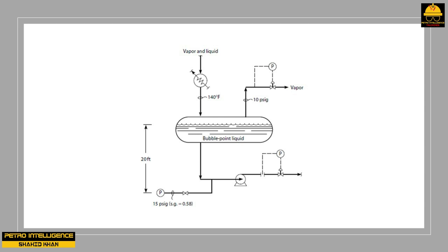As the flow control valve on the discharge of the pump is opened, the velocity of liquid in the eye of the impeller goes up. More of the pump's suction pressure, or feet of head, is converted to velocity or kinetic energy. This means that the required NPSH of a pump increases as the volumetric flow through the pump increases. The units of NPSH are feet of liquid head.